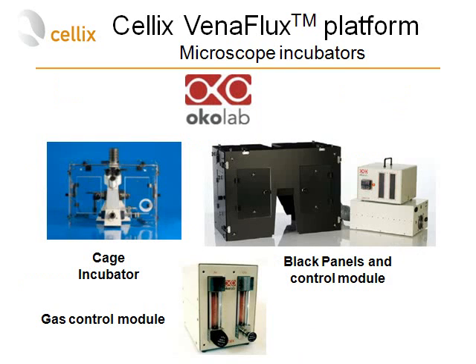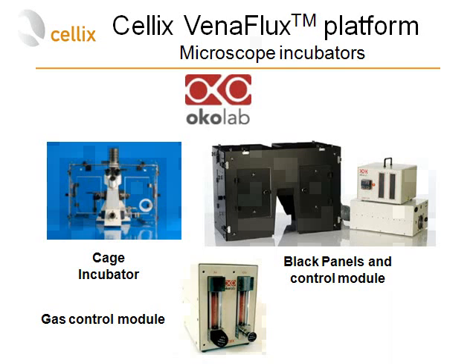The microscopes are typically fitted with cage incubators which allow a controlled temperature of 37 degrees inside the cage, so that all experiments within biochips are conducted in a 37-degree controlled environment. There is an option to fit the incubators with black panels so that without having a dark room you can conduct fluorescence experiments. There is also an option to fit the cage incubators with gas control modules which can mix air and CO2 in predefined quantities. This cage incubator is supplied by the company Okolab.